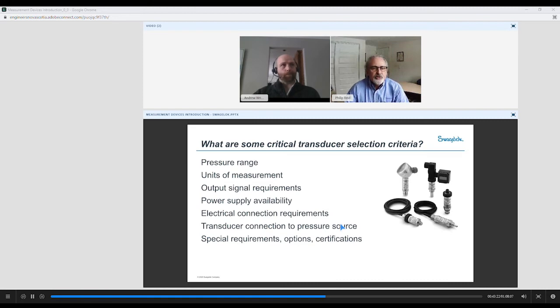Arrow here to move. So typically we just look for a little bit of information. If you're going to be looking to buy a transducer, you're going to want to know what that pressure range is going to be. You're going to want to know what units of measurement you're going to be working in. What output signal is required? Quite often, typically the 4 to 20 milliamp output signal. Is there a power supply available for instrumentation?